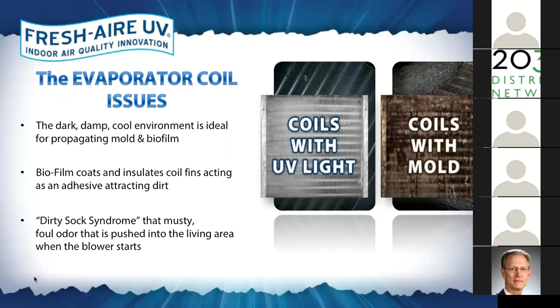So we used to sell and market UVC lights to keep coils and drain pans clean, and also providing some indoor air quality. So we used very low dosage of UV on coils and drain pans. So you can see the picture is very common in the industry. If anyone ever replaces a UV light and they're asked, how does the coil look? Everyone says the same thing, it looks brand new. So UVC lights, by not allowing anything to survive, any biofilm, it doesn't insulate the coils, it doesn't impact the coils, it keeps them 99.9% disinfected. This also helps with the dirty sock syndrome that occurs in parts of our country.